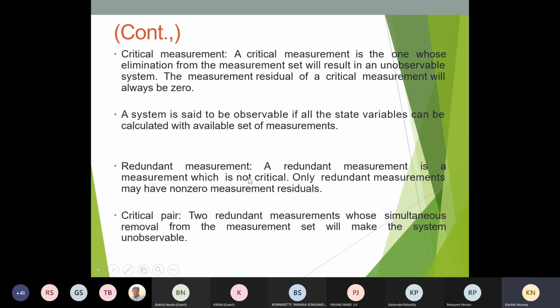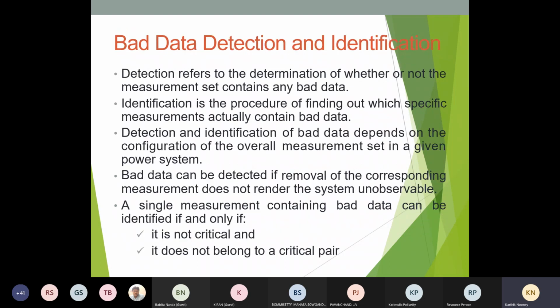A critical pair means if two such redundant measurements occur, then we can call them a critical pair: two redundant measurements whose simultaneous removal from the measurement set will make the system unobservable. That means we cannot identify the error, but it creates a disturbance in the power system. Those are called critical pairs.